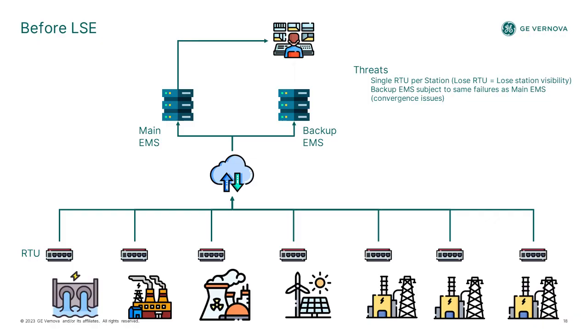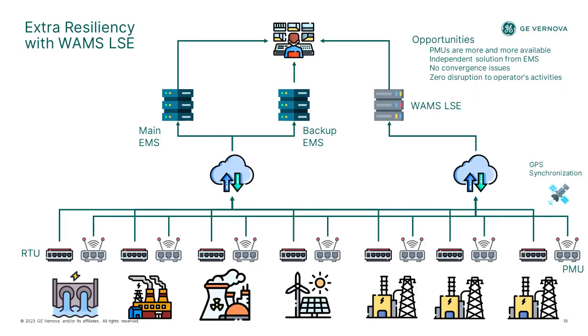But with WAMS, you have PMUs or relays or fault recorders, so independent devices from your RTUs that are gathering this data. Often the communication is separate from your SCADA data, and the WAMS applications are running on a separate physical server. So it provides that true end-to-end redundancy to your conventional EMS state estimation.